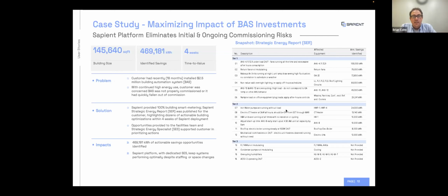What we found was things like air handlers that were just on 24/7. We found ones where they'd implemented a schedule to turn off at 5 p.m., but the BMS was viewing 12 a.m. as a new day and turning everything back on. Also things like return fans not modulating, or VFD issues.